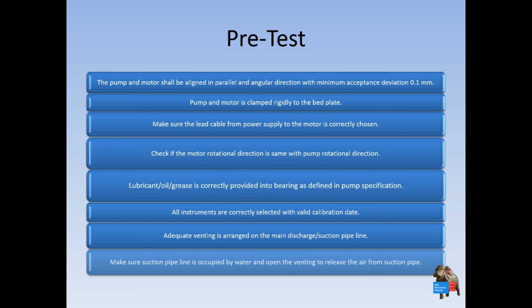Okay, then you also have to make sure that the suction pipeline is filled with water, and open the venting to release the air from the suction pipe. When you connect the pipe to the reservoir, usually there is still air there, so you have to vent it to ensure all the air is out of the pipe.